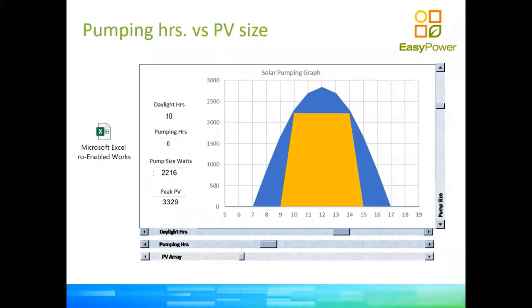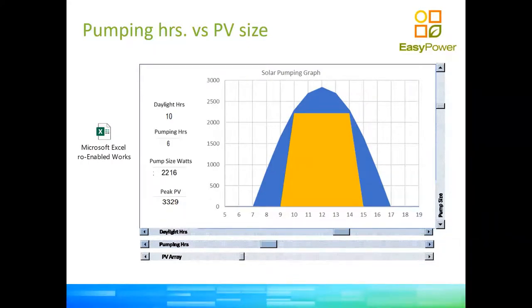This chart is graphic and straightforward. We have selected 10 hours of daylight, giving us that semi-approximate blue shape. We selected a random pump size of 2.2 kilowatts and a random solar array of 3.3 kilowatts. We've also played with how many hours of full-power pumping we want. The orange figure, flat at the top, represents your pump working at 100% rating — meaning you have enough power coming from the pump inverter for your pump to operate at 50 hertz.